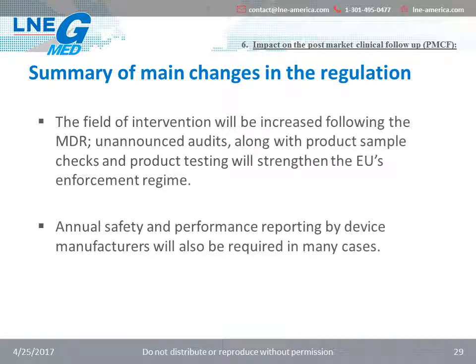Two things I just want to bring the manufacturer's attention to. The field of intervention will be increased following the MDR. What I mean is unannounced audits along with product sample checks. Product testing will strengthen the EU's enforcement regime. Also, annual safety and performance reporting by device manufacturers will be required in many cases.